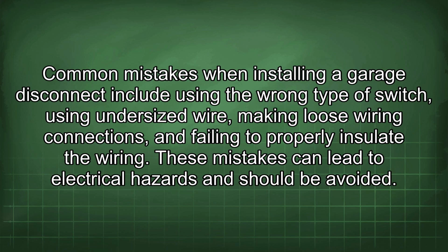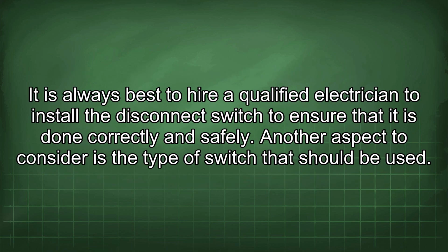Common mistakes when installing a garage disconnect include using the wrong type of switch, using undersized wire, making loose wiring connections, and failing to properly insulate the wiring. These mistakes can lead to electrical hazards and should be avoided. It is always best to hire a qualified electrician to install the disconnect switch to ensure that it is done correctly and safely. Another aspect to consider is the type of switch that should be used.